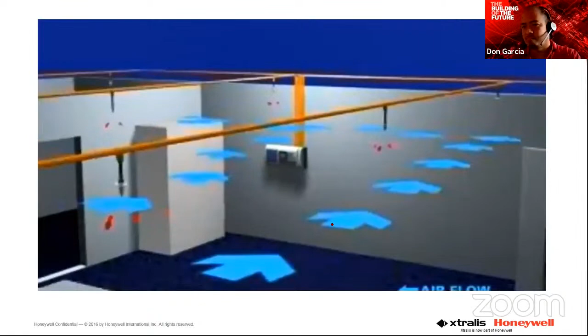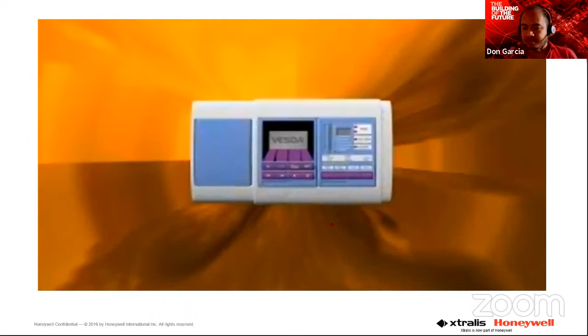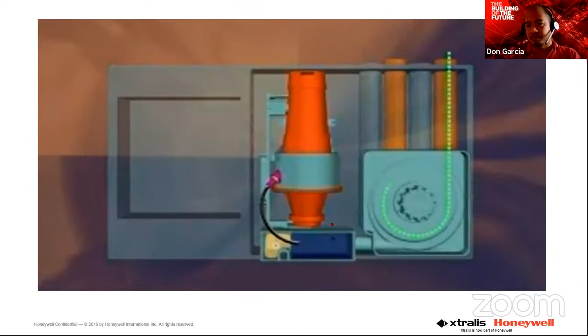So how does the VESDA detection system operate? Here's an overview. VESDA is an active system, continuously drawing air through multiple sampling holes along a network of pipes. These pipes transport the air to a central, highly sensitive detector. Prior to entering the chamber, the air sample passes by a flow sensor through the aspirator and a dual-stage filter.